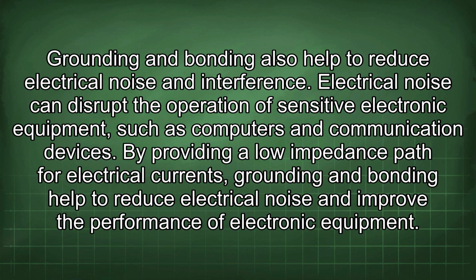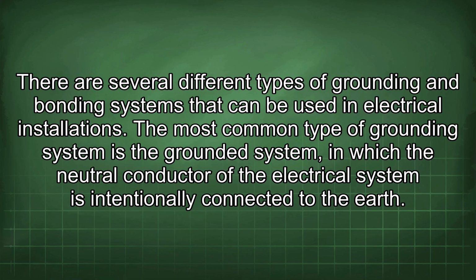Electrical noise can disrupt the operation of sensitive electronic equipment, such as computers and communication devices. By providing a low impedance path for electrical currents, grounding and bonding help to reduce electrical noise and improve the performance of electronic equipment. There are several different types of grounding and bonding systems that can be used in electrical installations. The most common type of grounding system is the grounded system, in which the neutral conductor of the electrical system is intentionally connected to the earth.